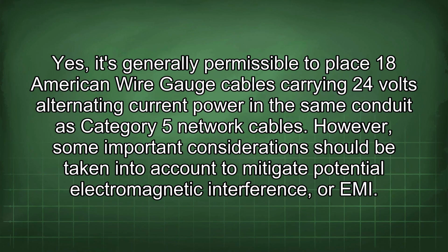Yes, it's generally permissible to place 18 American wire gauge cables carrying 24 volts alternating current power in the same conduit as Category 5 network cables. However, some important considerations should be taken into account to mitigate potential electromagnetic interference, or EMI.